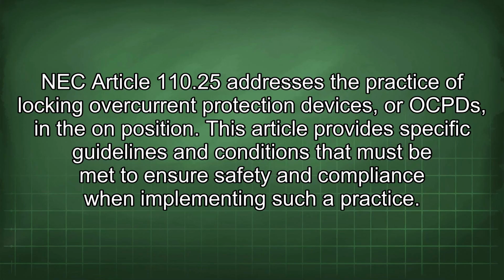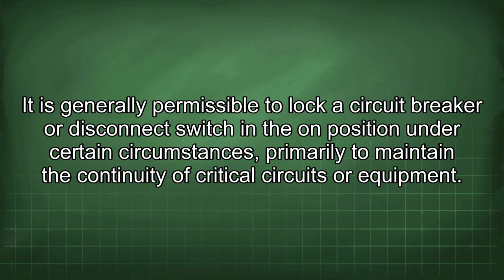NEC Article 110.25 addresses the practice of locking overcurrent protection devices, or OCPDs, in the on position. This article provides specific guidelines and conditions that must be met to ensure safety and compliance when implementing such a practice. It is generally permissible to lock a circuit breaker or disconnect switch in the on position under certain circumstances, primarily to maintain the continuity of critical circuits or equipment.